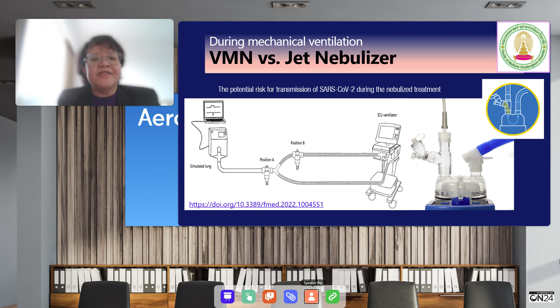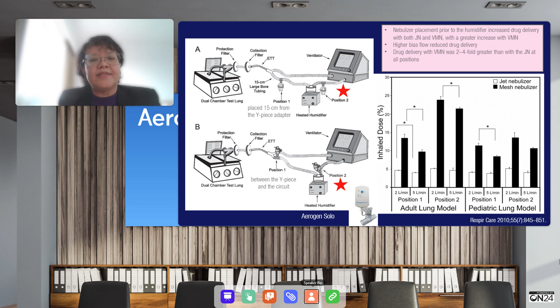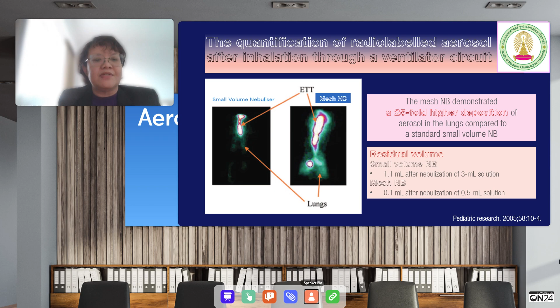And we did not allow the use of jet nebulizers during mechanical ventilation because it requires disconnecting the ventilator circuit. Although a jet nebulizer can be placed prior to the humidifier, drug delivered with the mesh nebulizer was 2 to 4 fold greater than with the jet nebulizer at all positions. Overall, the mesh nebulizers demonstrated a 25-fold higher deposition of aerosol in the lungs compared to standard nebulization, with a lower residual volume.